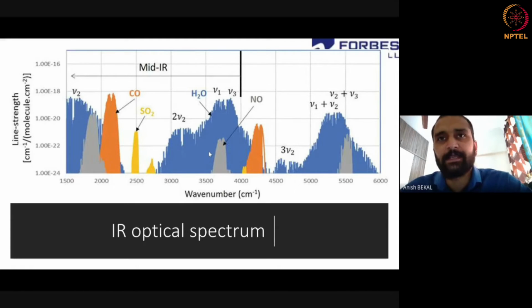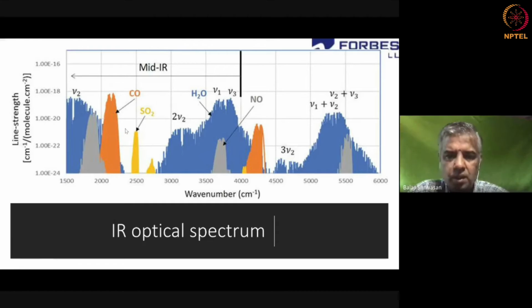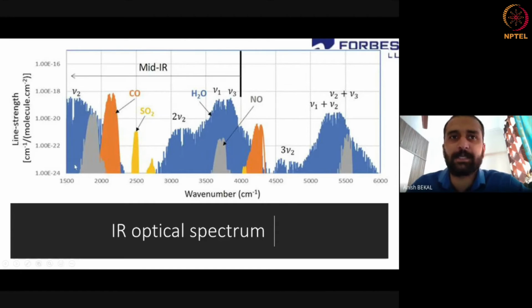The nice thing about the UV region for SOx/NOx measurement is that there is practically zero interference from moisture, so you can do a very good measurement there. But if you look at line strengths in the mid-IR region, they are almost comparable to those in the UV region. The problem is that sources there are very difficult to get or very costly. So most sensors in the market today are either in this region, or they are broadband sources -- these are the two options that exist.